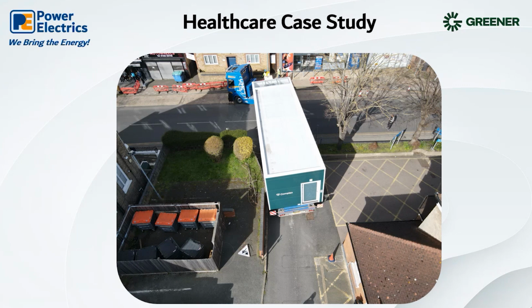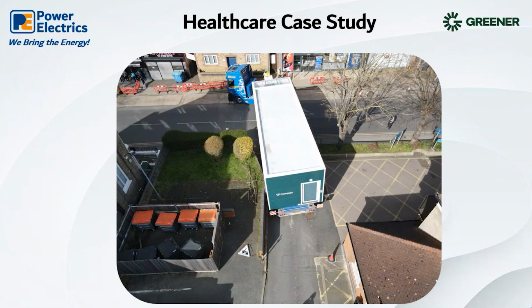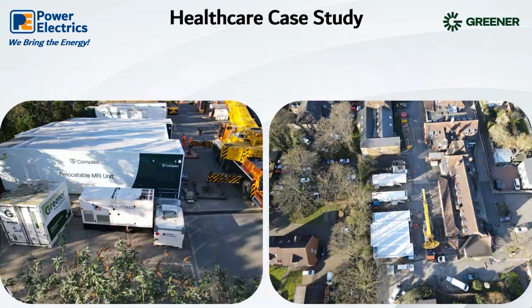Very problematic for generators to accept sudden impact loads, so you have to go up in the size of the machine to do it. As you can see from some of the images that Sam's putting through now, this particular project had very tight access issues, as well as a lot of local residents and also a hospital recuperation centre very nearby. So as Dan said earlier, the major benefit of using batteries is to handle the large spikes. So the 4 units where we had 2 CT scanners, an MRI and a support unit would have normally resulted in at least 2 300 kVA generators or even a 500 kVA running.